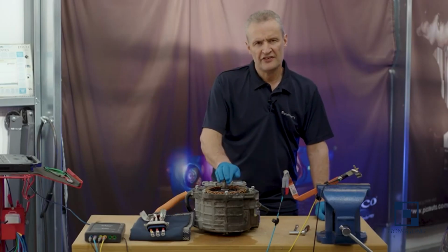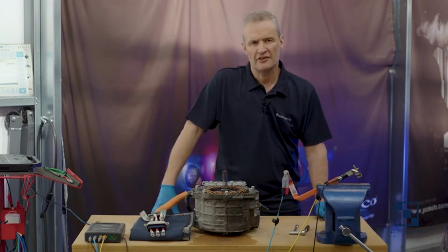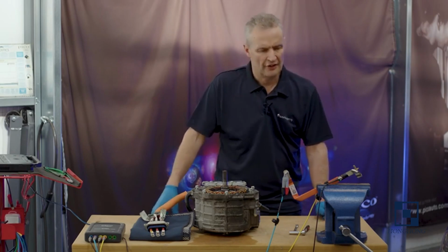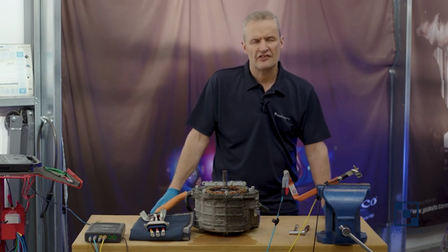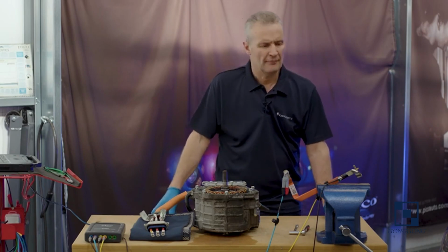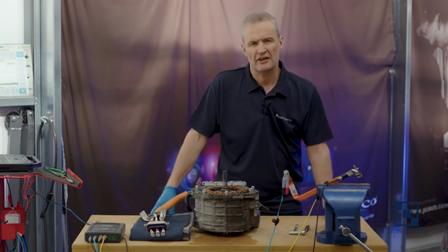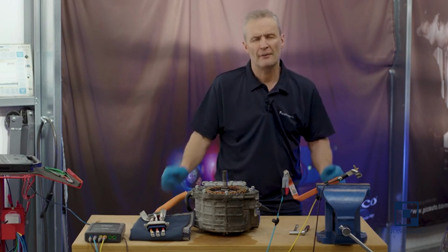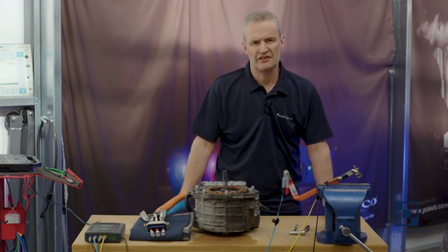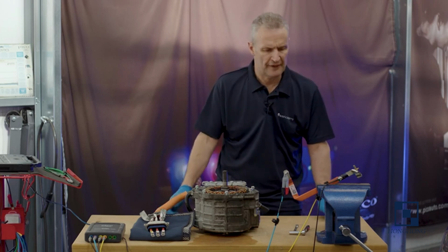Moving on from the phase testing of the motor using the milliohm and motor tester, we're now going to look at the resistance of a bus bar. Equally this could be a ground lead. Anywhere where we need to measure with milliohm resolution the resistance of such a lead or a bus bar.